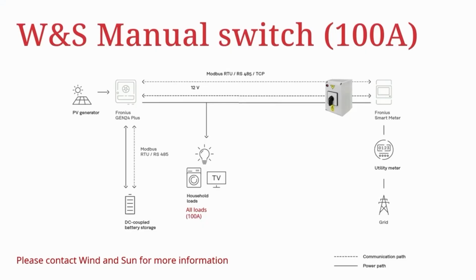But if you need to go onto a larger system where you want to be able to back up an entire 100 amp residential installation, we have a couple of solutions available from third-party suppliers. So Wind and Sun, our distributor, have produced a manual switch which would fit between the Fronius smart meter and all loads on site. This device operates in the same way as the Fronius backup switch, however it has a 100 amp breaking capacity, which means it can be installed right after the Fronius smart meter and include all consumers on site. Just be aware that if you have something like an EV charger or a heat pump, you need to make sure those are switched off during the backup mode to avoid draining that battery unnecessarily.